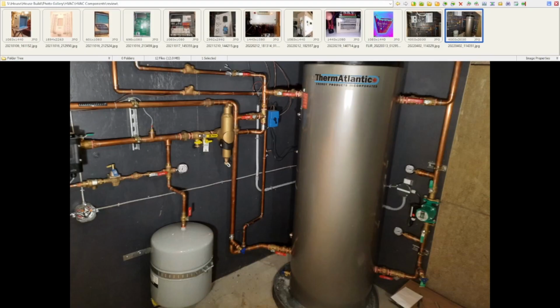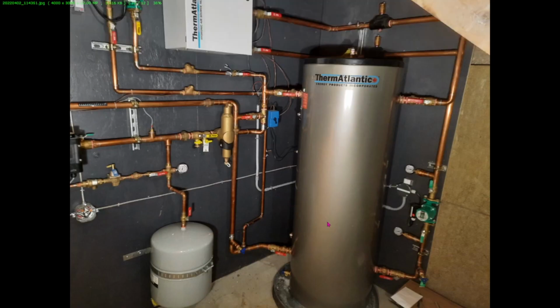And then we have, to the right of the DX2W, the 105 gallon storage tank. We've got the relay controlling the circulator. This is the Wilo Star supplied with the DX2W. This is the loop that goes between the DX2W, which is just off screen here, and the buffer tank. So now let's look at the actual software that is utilizing all of this.